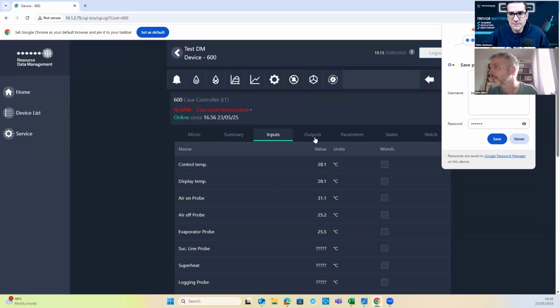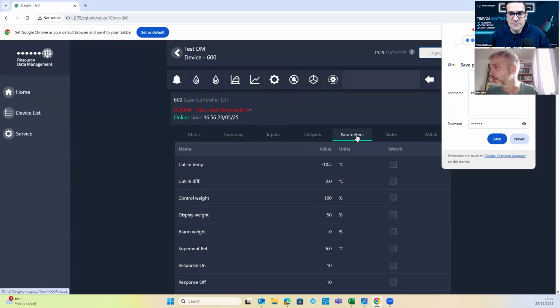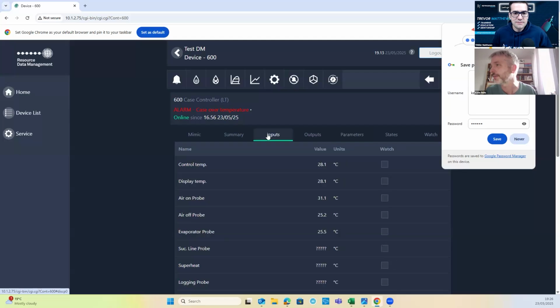So, right, let's wait for that value to update properly, which it will do in a moment. As it took my parameter change, let's have a look. Right, control weight 100%. So eventually, when that gets a grip of itself and updates, the control value is going to go to the air on, because I've raised the temperature of the air on now. It's just the speed it updates. It will eventually end up at the air on, and you'll get those two values reading differently. 31 Celsius now and 25. So when it eventually updates itself, there we go. Right, it's got a grip of itself now.